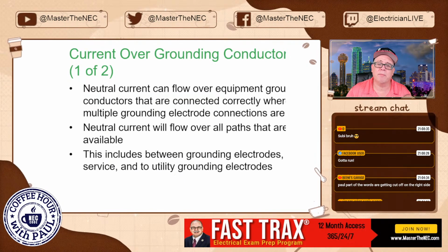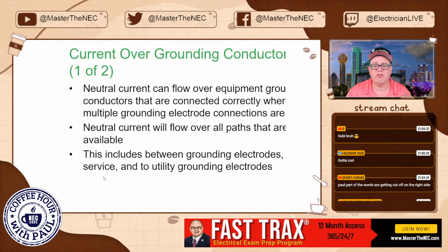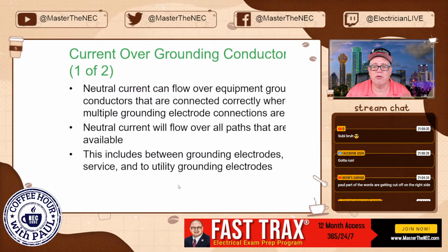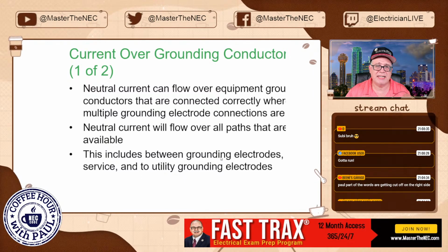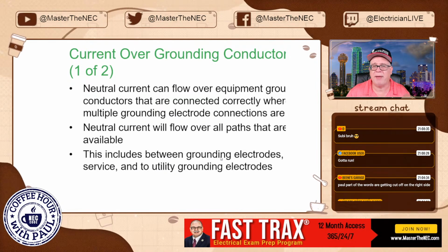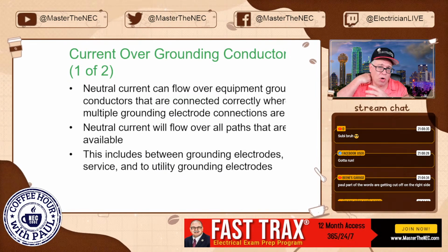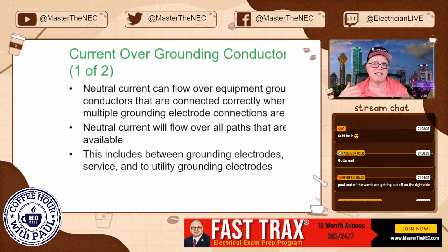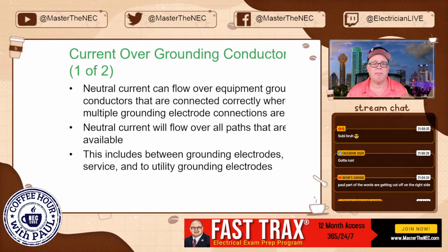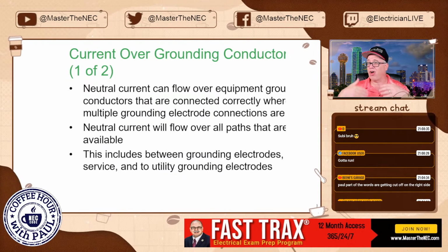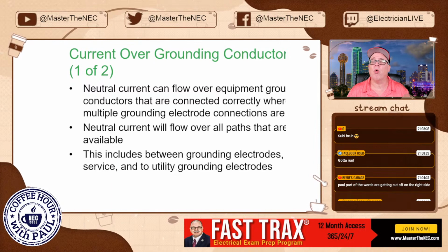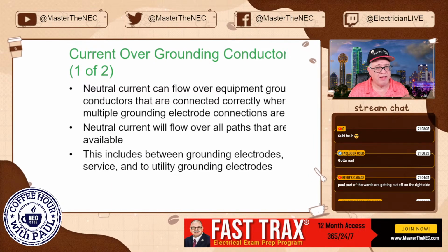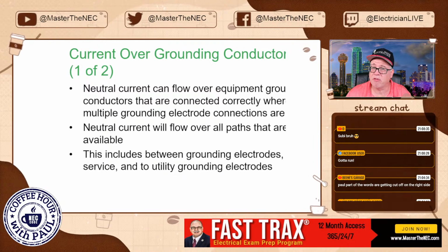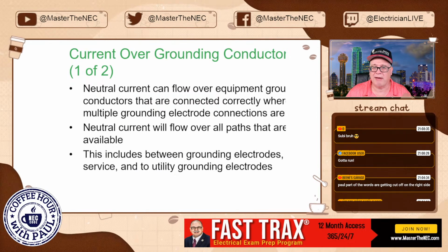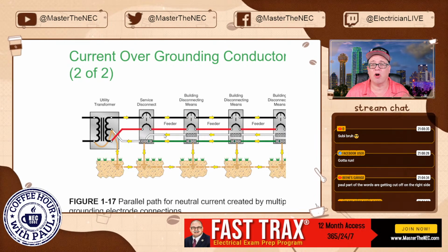Now, this includes between grounding electrodes to the service and to utility grounding electrodes. So again, current is going to travel on all paths available. And just remember the old golden rule. All current doesn't take the path of least resistance. It takes all paths proportional to the impedance of that path. If you have a really good low impedance path, you're going to have most of the current travel on that path. And that's what we're charged with constructing.